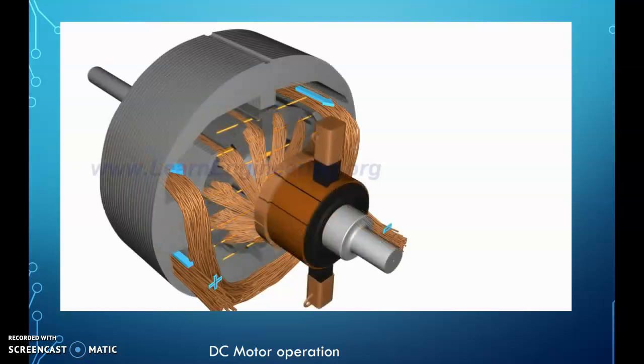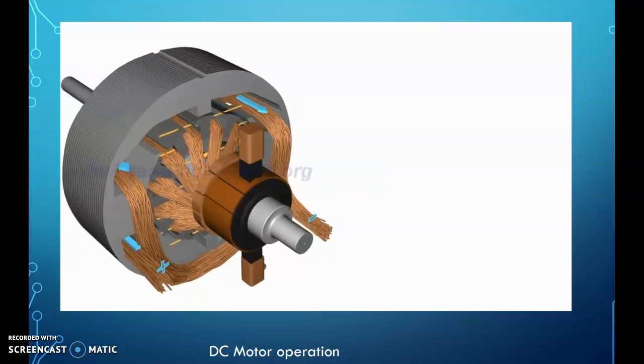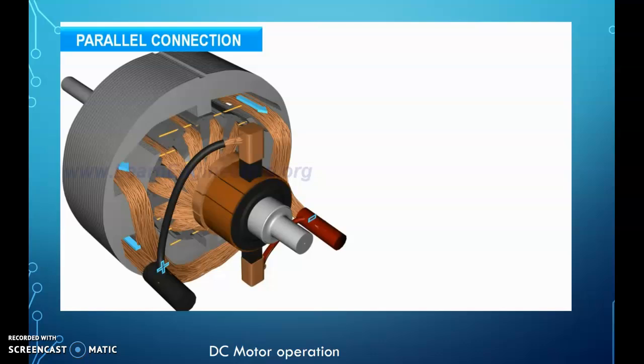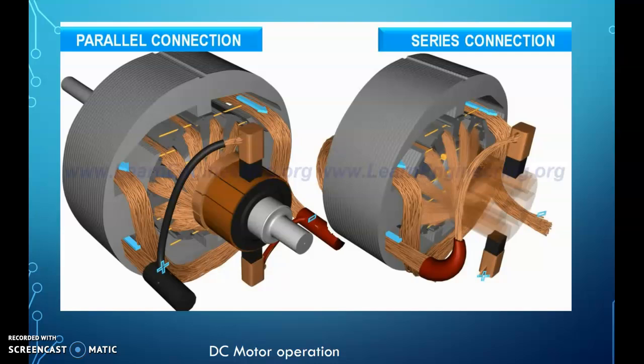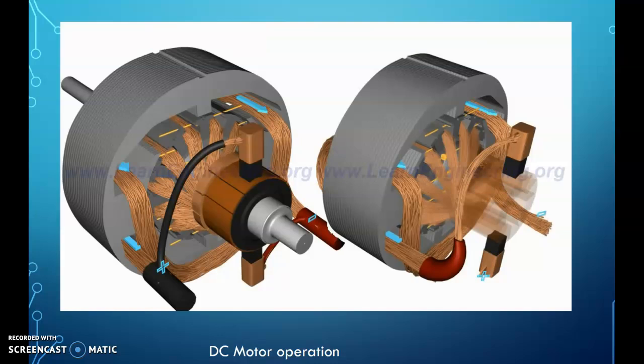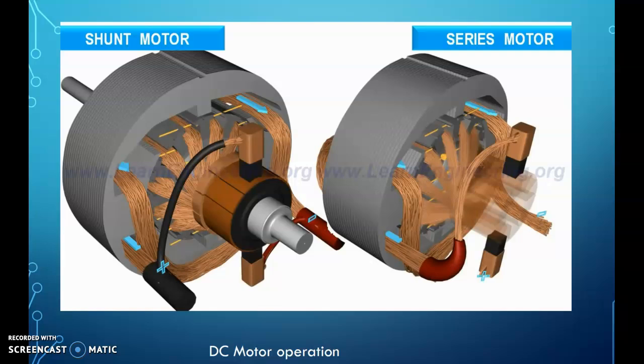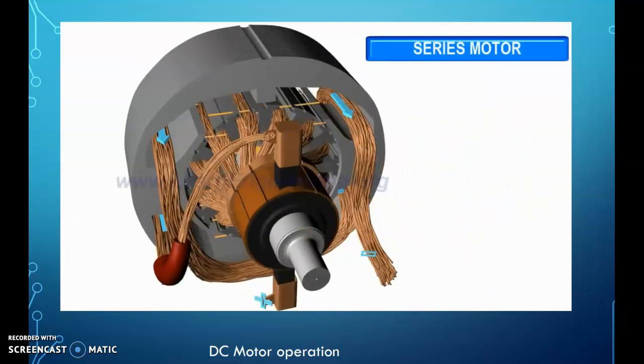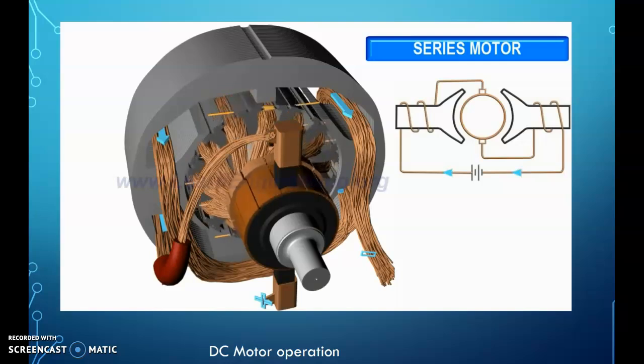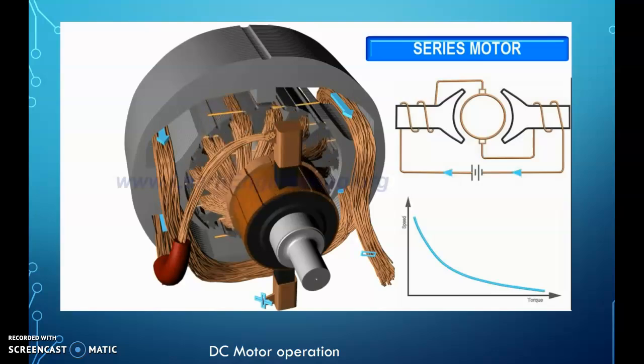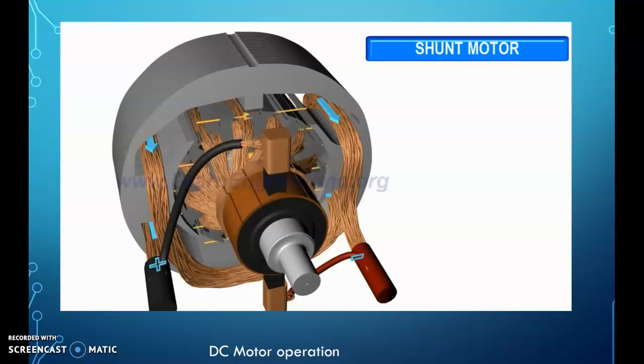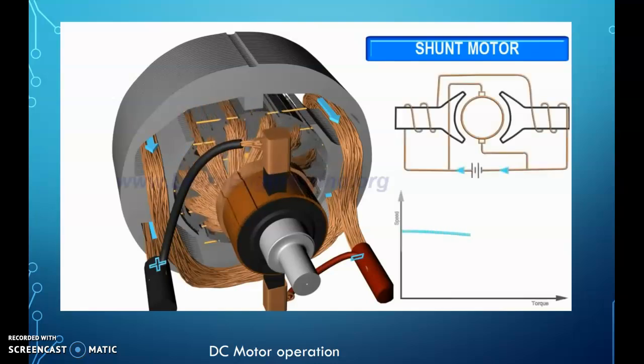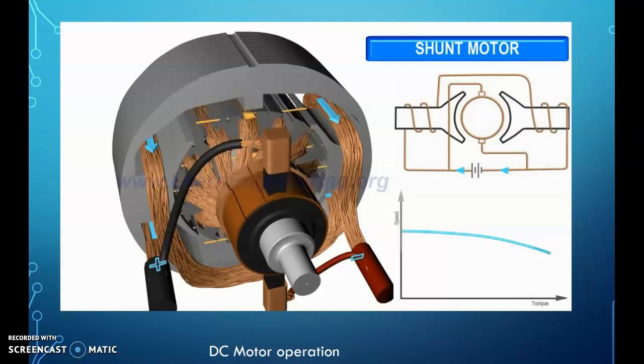The field coils can be connected to the rotor windings in two different ways: parallel or series. The result is two different kinds of DC motor construction, a shunt and a series motor. The series-wound motor has good starting torque, but its speed drops drastically with the load. The shunt motor has low starting torque, but it is able to run almost at constant speed, irrespective of the load acting on the motor.